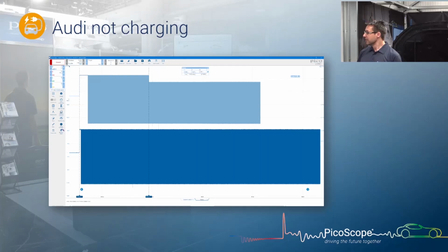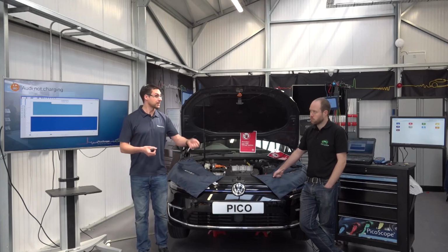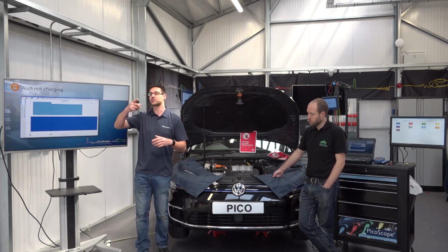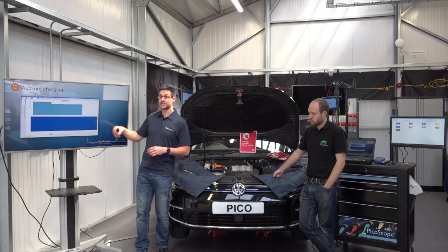First one to check then is to look at that CP signal and see what's coming in. So we know that using the EV guided test, we have a known good. We can see that step change, as we mentioned earlier. The top one is the reference waveform from the guided test, which is easy to create within the PicoScope 7 software. And in the darker blue colour, that's the live signal that we took off the vehicle. So you can quite clearly see that we get that 9-volt drop, indicating that the charger has been connected. The car's set that voltage level, but we get down to a -12, so the EVSE is now outputting that oscillating -12, +12, but we obviously get that drop to 9. But then it doesn't do this next part. This change to 6 volts then indicates that the car is ready to accept a charge. We don't get that happen.